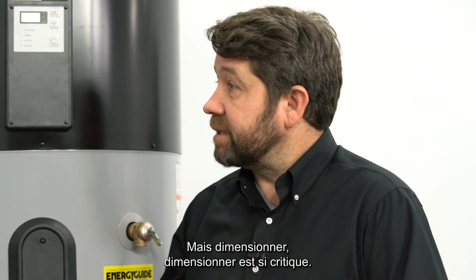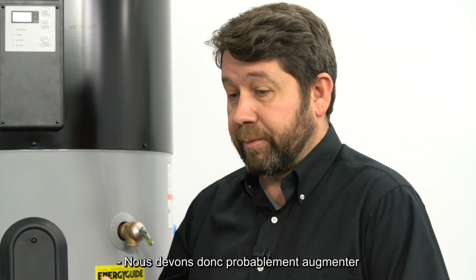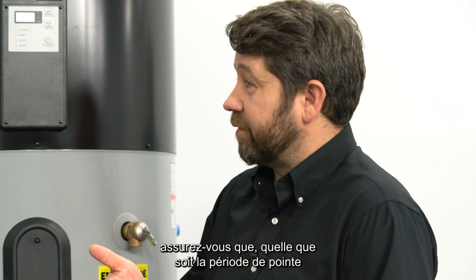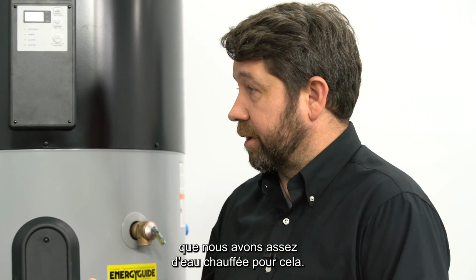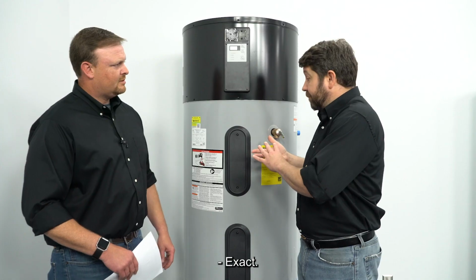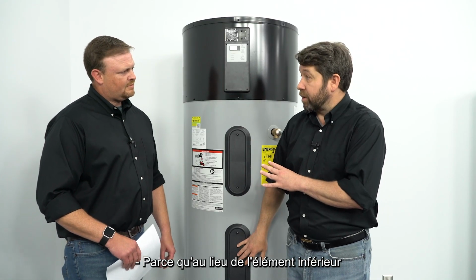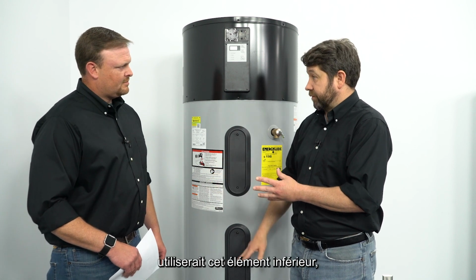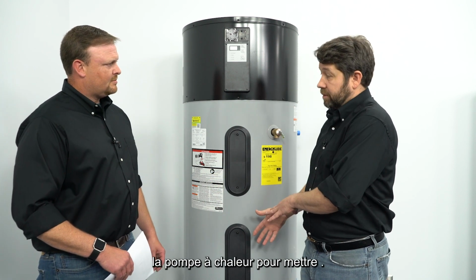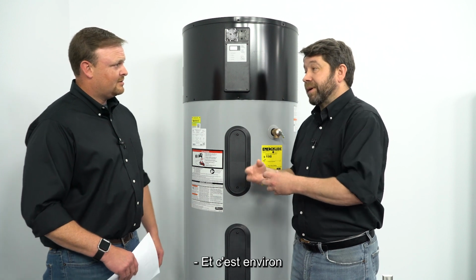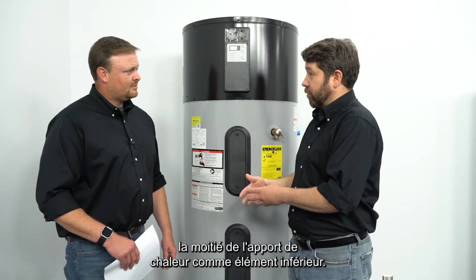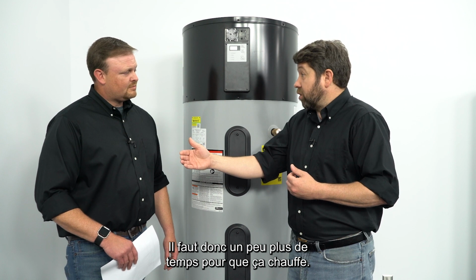But sizing is so critical. So we probably need to go up in size a little bit from what you might be used to with an electric water heater. Make sure that in whatever peak period that we're going to use hot water, that we have enough water heated for that. That way we'll have time for the recovery. And that's going to be the other side of this. In lieu of the lower element, where a traditional electric water heater would use that lower element, we're using the heat pump to put in, and it's about half of the heat input as a lower element. So it takes a little bit longer for it to heat up.